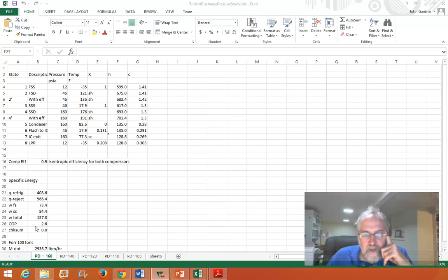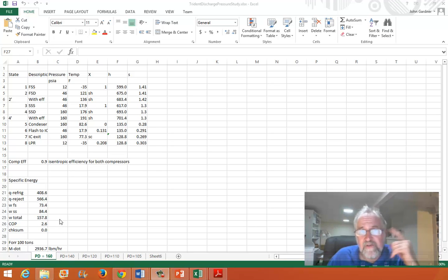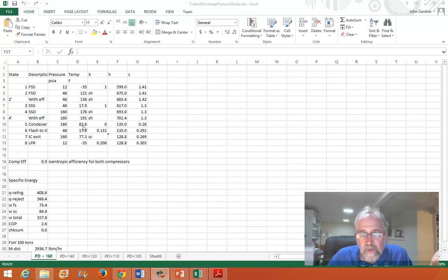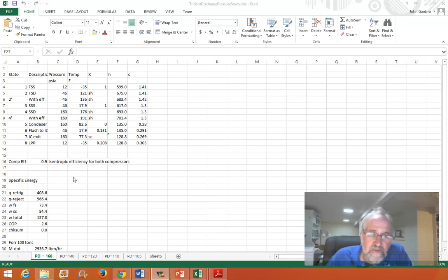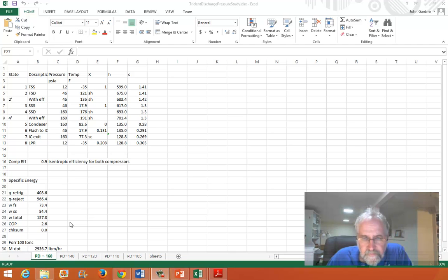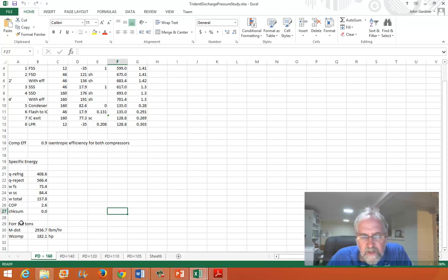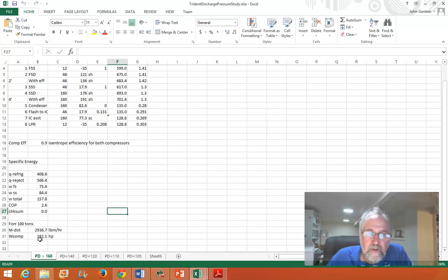The coefficient of performance is 2.6, which is actually pretty low, but it's a huge lift — going from minus 35°F to 82°F saturation temperature at discharge pressure, so a really large temperature lift. A low COP shouldn't be too surprising. For 100 tons of capacity using these specific values, the compressor work would be 182 horsepower, so that's 1.82 horsepower per ton of refrigeration capacity — that's the other index of performance used in industrial refrigeration.